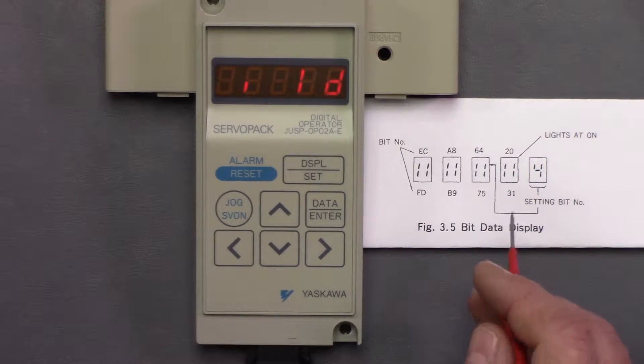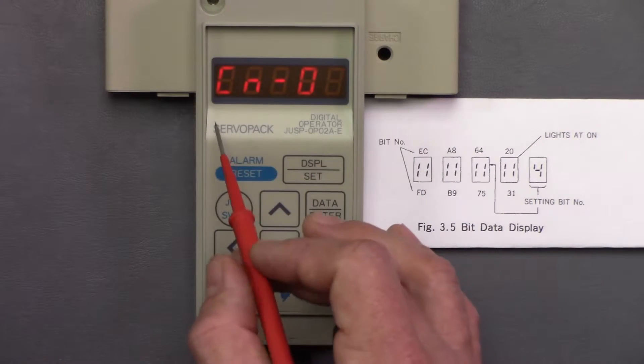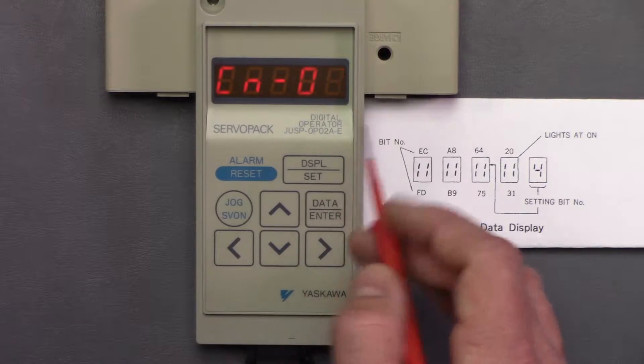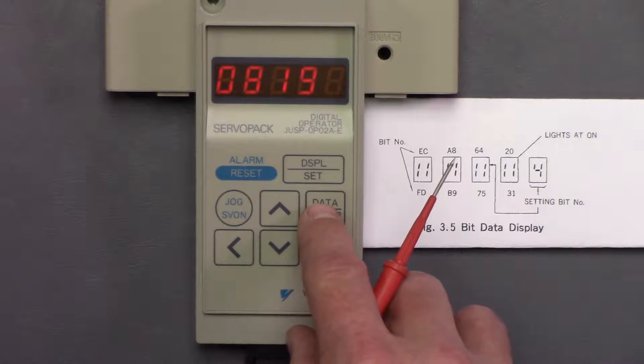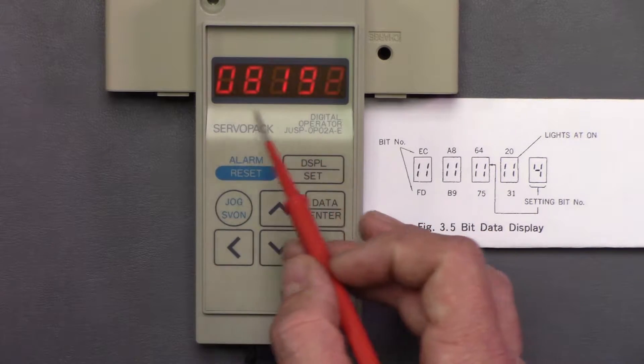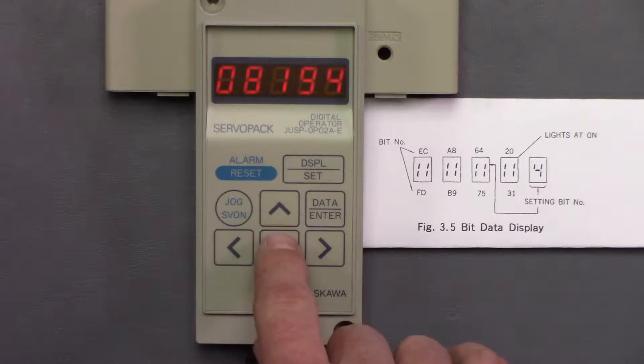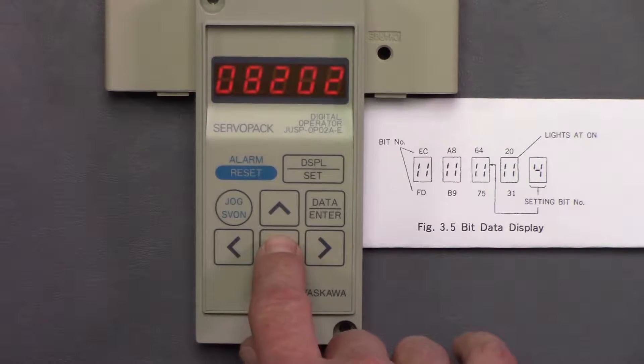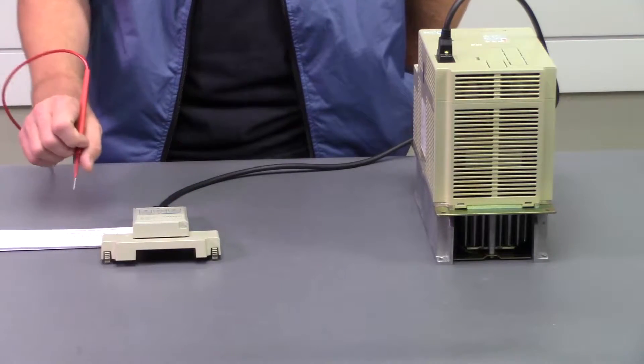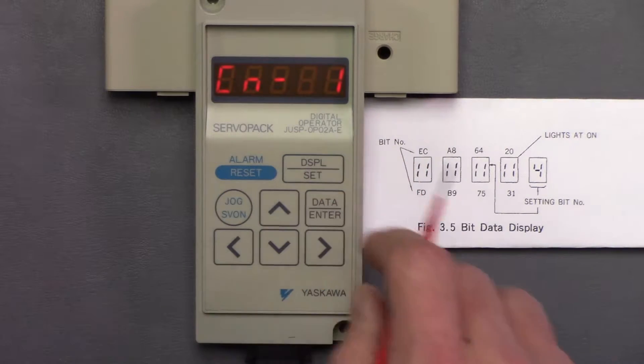To get back into the main status, you'll hit data enter, and it's going to bring you back to the CN. So the next thing we're going to do is go into CN11, hit data enter. This is another parameter that can be edited, and this is a little bit simpler because all you do is use the arrows to toggle the values up and down. So I'm going to leave this at 8192. That's where it needs to be. If we were to make a change, we hit data enter, it'll save, hit data enter, brings us back to the CN function.